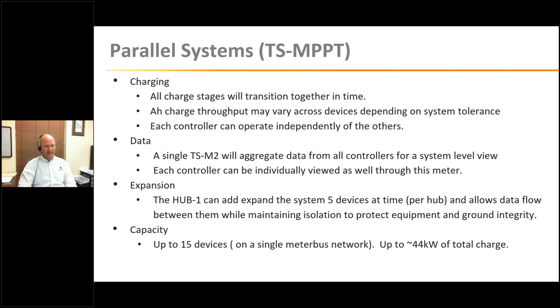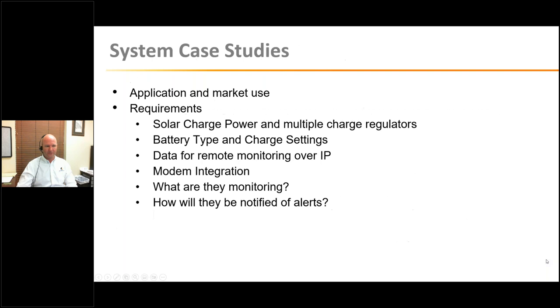The hub, as I said, adds that expansion capability and isolation while allowing the data connectivity. And up to 15 devices - I did the quick math, and that's around more or less 44 kilowatts of power in a single off-grid system. So a very, very large one at that, definitely pushing the limits of a 48 volt battery, but definitely can get the job done.